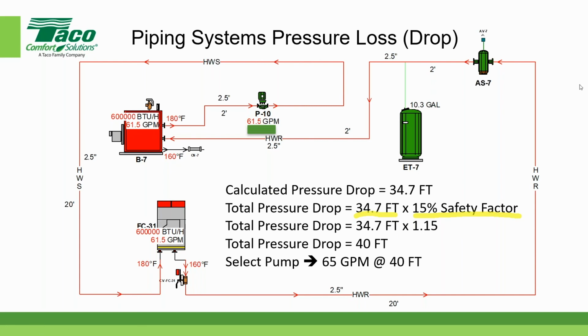Any questions? Just one comment about the more complex one. You should do them all, but you make sure you do the worst case, right? For sure. That's correct. So when you're doing a manual calculation, you might have 4 different circuits or paths, in which case you'd have to do the pressure drop calculation for each path, and then we'd pick the one with the worst case. So in our case, let's assume that this was the lowest value, 34.7. If I had 4 different circuits or paths, and let's say they range from 34.7 to a maximum of 50, then I would use the 50 feet as the calculated pressure drop.